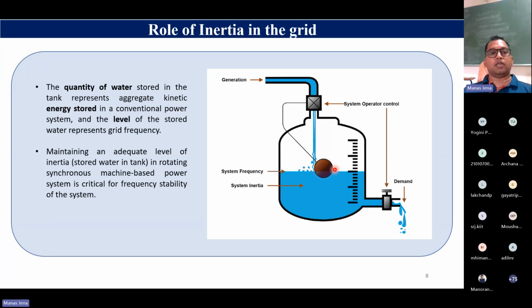So you can think of the scenario, maintaining an adequate level of inertia, that means the stored kinetic energy, will be helpful in case of, say, a contingency where you don't get any generation. So let us say you stop this inflow of the water, but demand is still there, load is still there. If you have a higher amount of water inside this vessel, then the reduction in the frequency will be less compared to if you have less volume of water inside this. So that is what is also happening in the grid.